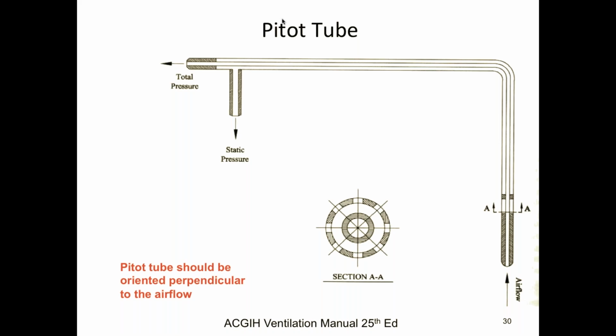Velocity pressure is the pressure that you feel when air is moving and it hits you. For instance, the wind, right? If you stand out in the wind, you feel pressure from the air moving and hitting you. That's called velocity pressure. Here, when you're standing here, the static pressure is 14.7 psi. The static pressure is the air pressing on our body from all directions. It's always pushing against us. Velocity pressure is when the air is moving and hitting us, and we can feel that pressure from that air hitting us. You add the two of them together, and you get something called total pressure. It's the sum of the static pressure, which is acting everywhere, and the velocity pressure, the pressure from the air pushing against you.